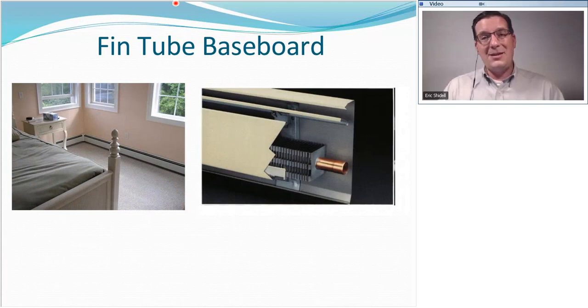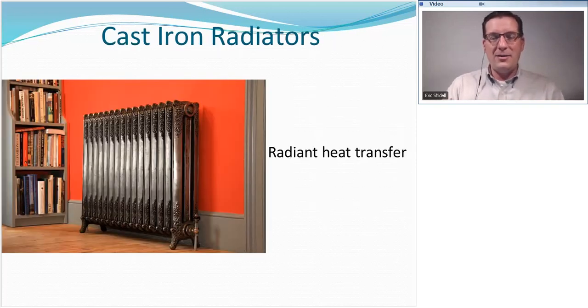This is like the one thing that's kind of cool about boilers: you'll notice that the heat source and the heat emitter are mirror images of one another. So the copper fin tube baseboard is a mirror image of the copper fin tube heat exchanger. The cast iron radiator is a mirror image of the cast iron sectional boiler. You can see the sections here bolted together. It's the same idea. Water in on the bottom, out on the top. Sometimes in on the bottom, out on the bottom.